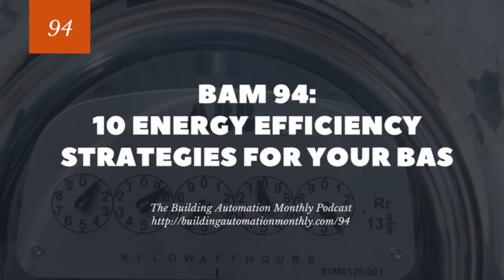which then means you're going to have to heat the air up. An even worse example of this is when you have no economizer control strategy and you just keep the economizer set at a certain percentage. So you're bringing in hot outdoor air and cooling that outdoor air, and then you're having to heat that outdoor air back up. Now, the really nasty version of this, and you see this more on fan coils, is where the heating and cooling process loops get out of whack. Maybe they're misprogrammed, maybe they're not properly tuned, but for whatever reason, you have heating on and cooling on at the same time, and they're fighting each other.